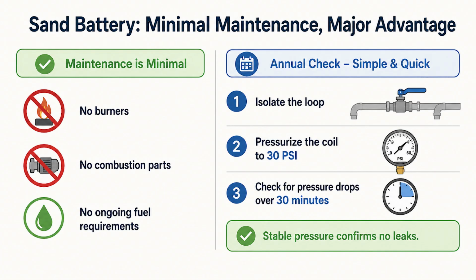Maintenance is minimal and represents a major advantage. There are no burners, no combustion parts, and no ongoing fuel requirements. Annually, isolate the loop, pressurize the coil to 30 pounds per square inch, and check for pressure drops over 30 minutes. Stable pressure confirms no leaks.